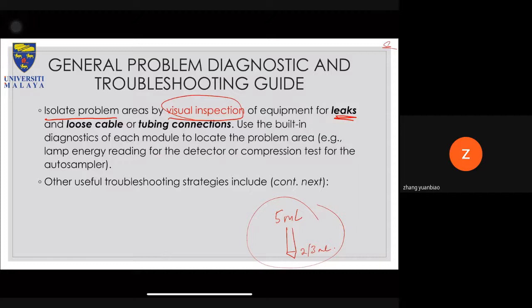Okay, you can also check for loose cable or tubing connections, meaning that if you look at the system, there are at least 6 modules interconnecting with one another. So sometimes, if you just focus on the column itself, and you keep switching from one column to another, there is a very high chance that when you put the tubing into a new column, the tube was not properly engaged. Therefore, it's a bit loose and leaks might happen.